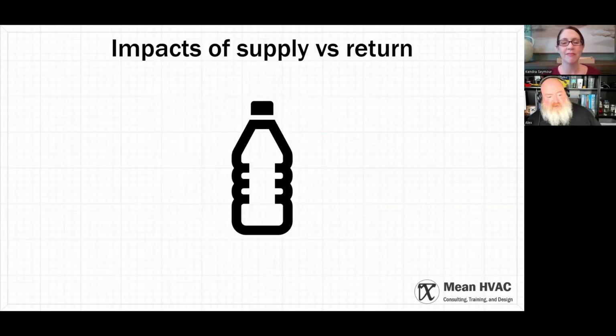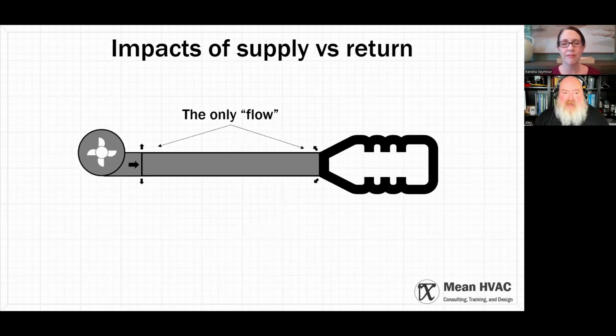Supply versus return: supply is super important for the flow pattern of air in the space. Return is super important for pressure relief—not to affect the flow of air in the space, but to affect the ability to even flow into the space at all. If I had a blower attached to this water bottle and no return path, it would probably stall the motor and give me a puff of blue smoke. But you might get a little leakage here and a little leakage there.